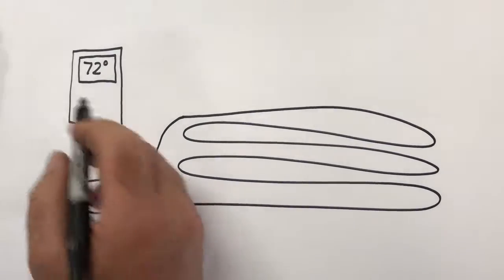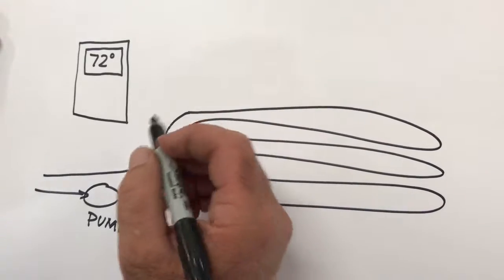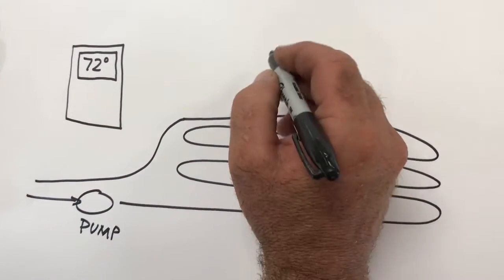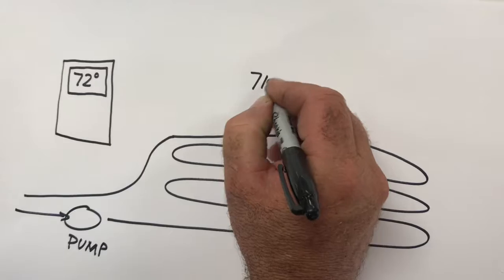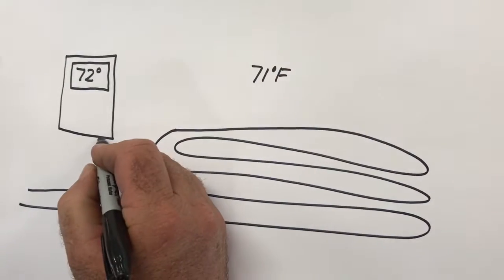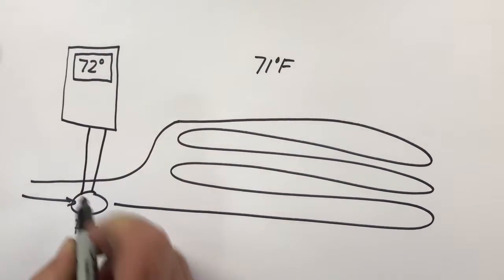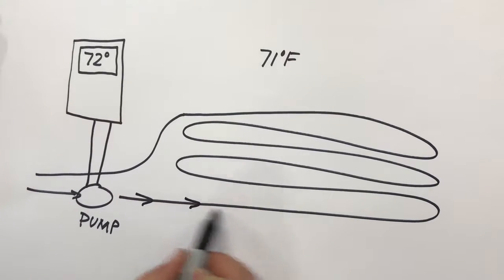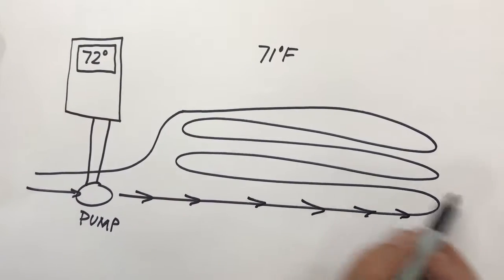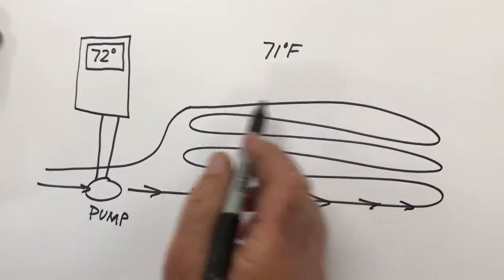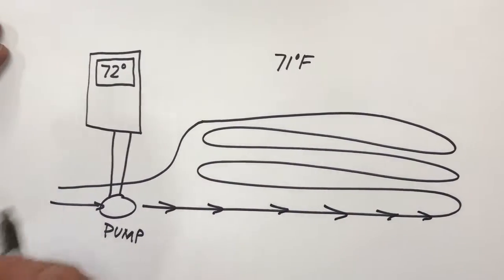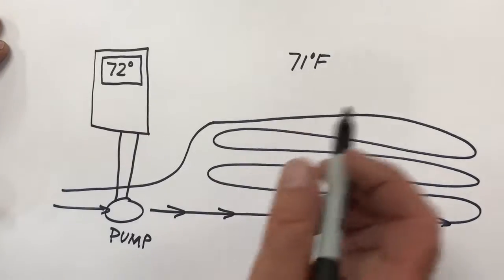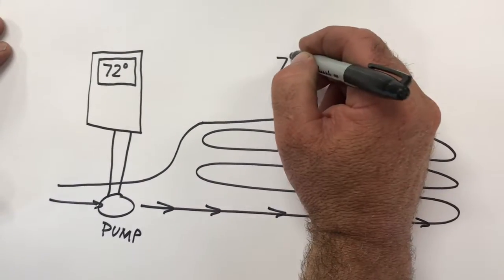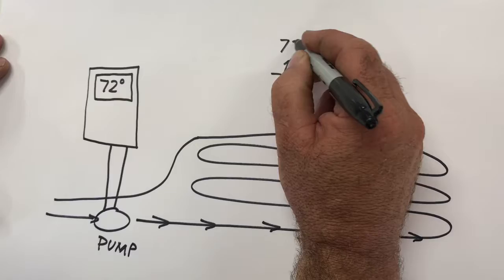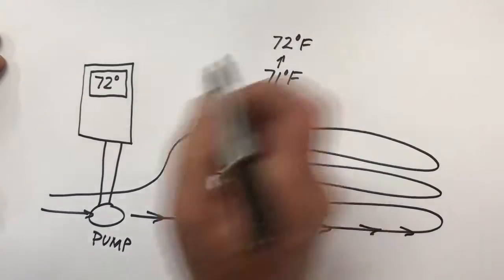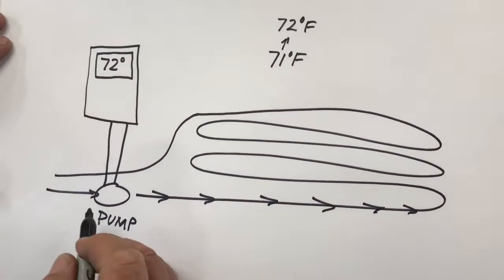So when the thermostat detects that the room is colder than 72, let's say 71, it is going to energize this pump, which is going to send some hot water through the floor network and warm up the room, and then go back for heating in your solar heating system. So technically, as soon as that temperature rises to 72, then the thermostat will shut off the pump.